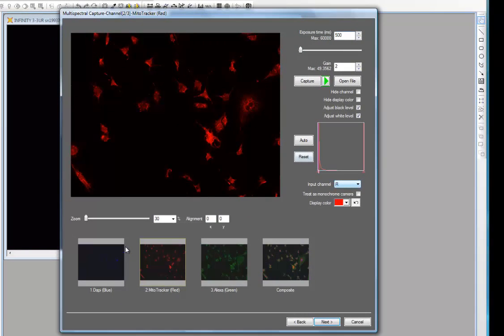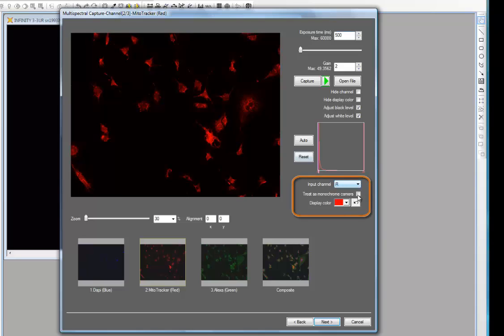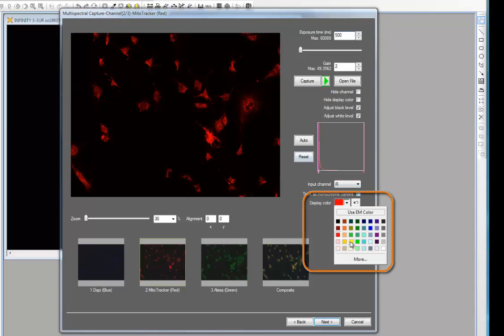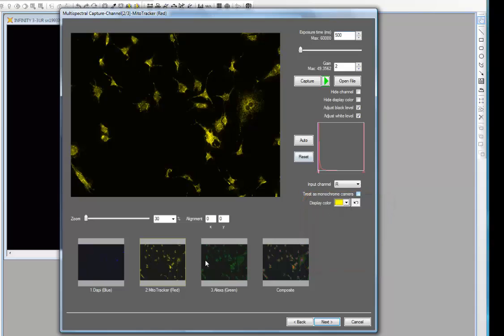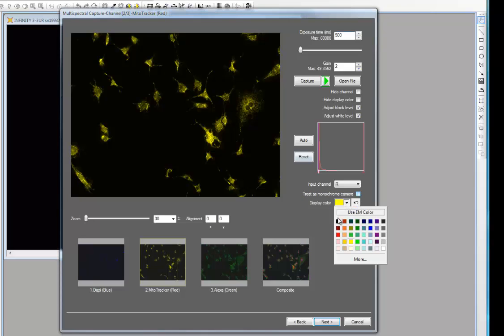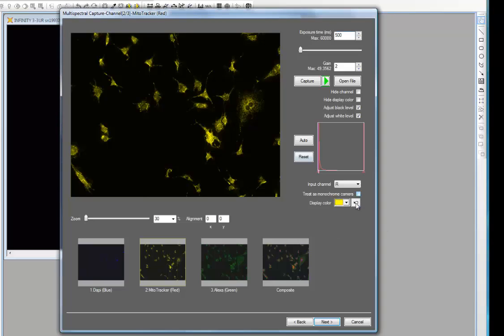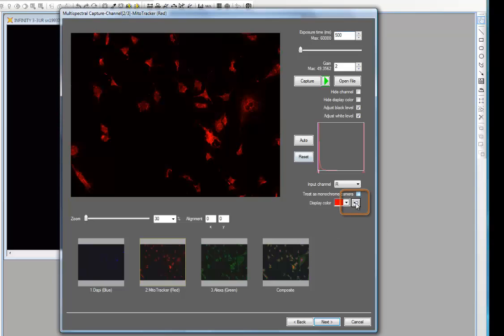Some dyes will emit a sort of a magenta color, or a purple color. Other dyes will emit a yellowish color. In which case, you need to have the camera receiving on more than just the red, or the green, or the blue channels. And in these cases, enabling the camera to be treated as a monochrome camera will give you a better range of result, in which case your channel setting would have chosen a display color that would more accurately reflect the output of that channel. You can switch the output color channel just by simply selecting a different display color than the one defined in your camera settings. If you want to return to the original defined color for this channel, simply click on this return button.